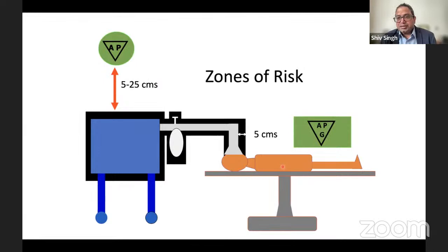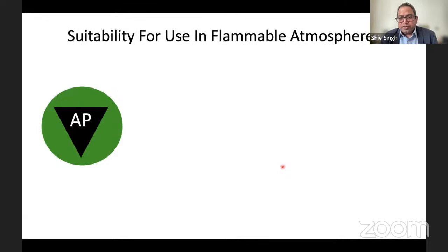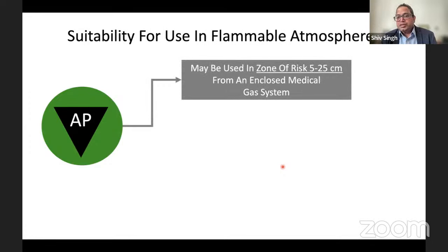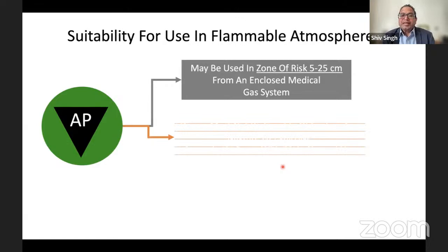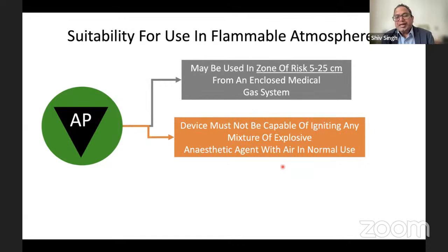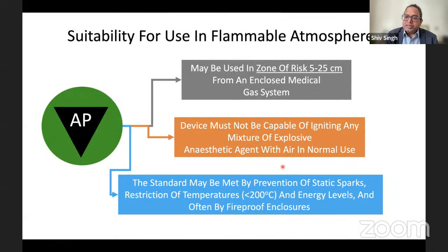Anesthetic proof equipment is suitable for use in a flammable atmosphere. We don't have flammable atmospheres now in the operation theaters. We don't use the old ethers, which were flammable, or trilene. We have new ethers, but they are not flammable. So AP can be used within the zone of risk of 5 to 25 centimeters. Devices must not be capable of igniting any mixture of explosive anesthetic agent with air in normal use. It is also based on surface temperature, which is restricted to less than 200 degrees Celsius. And there should be no static sparks. That is, they should not cause fire even with a static spark.